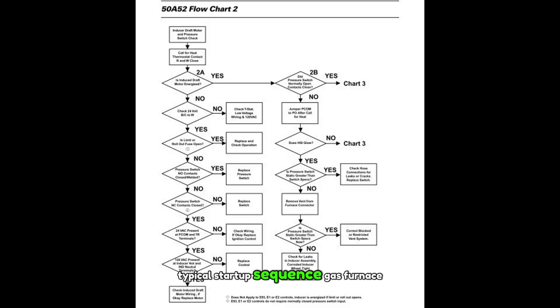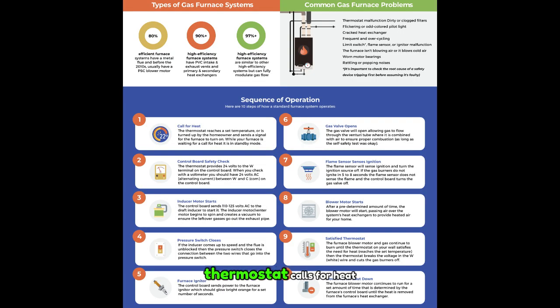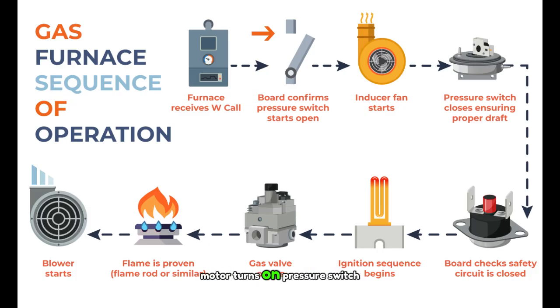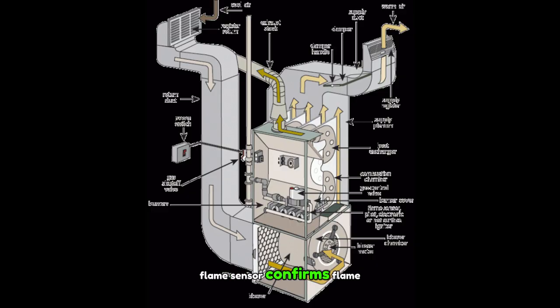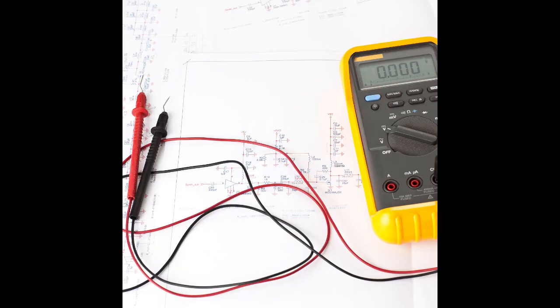Typical startup sequence, gas furnace. Let's review a basic startup timeline. Thermostat calls for heat, W-wire energizes, inducer motor turns on, pressure switch confirms airflow, igniter, hot surface or spark, activates, gas valve opens, burners ignite, flame sensor confirms flame. Blower motor turns on after a delay. If any step fails, the board will shut down the system and may flash a diagnostic code.